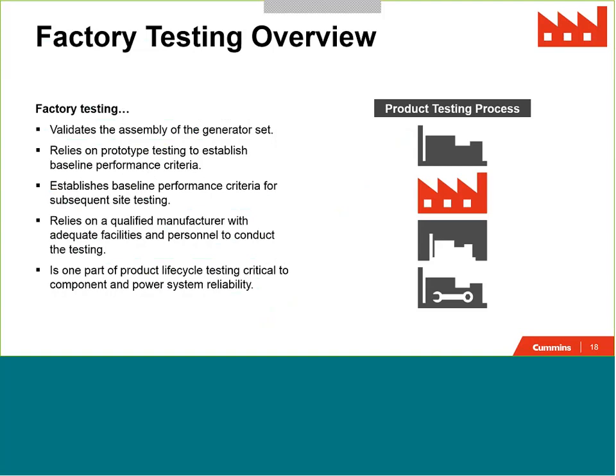Factory testing relies on prototype testing to have established a baseline performance criterion. So a factory test is going to look back to prototype testing to ensure the product is performing as expected. Factory testing also establishes a baseline performance criteria for the subsequent site testing. So site testing, when conducted, is going to look back to our factory testing to ensure it's performing as expected. Another key point here, factory testing relies on a qualified manufacturer who is capable of conducting the test, has adequate facilities, and the personnel to actually conduct the testing. And again, factory testing is just one part of the product testing life cycle, and it's critical to the reliability of the power system.